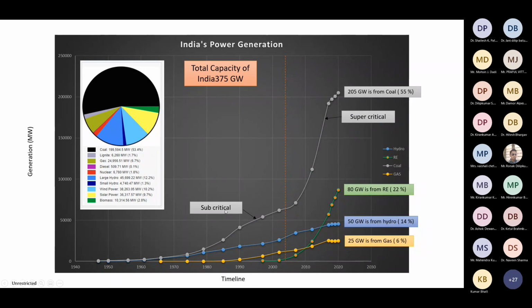Earlier the turbines and boilers were mainly subcritical, meaning low pressure, high temperature, like 540 degrees Celsius and roughly 180 bar capacity. So efficiency was low. But then new R&D happened in steam turbines so we could go up to supercritical pressures, beyond 230 bar and 565 degrees Celsius, which improved the efficiency of the overall power plant and reduced carbon emissions.